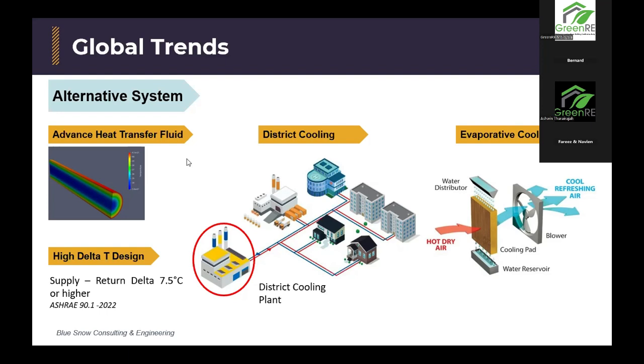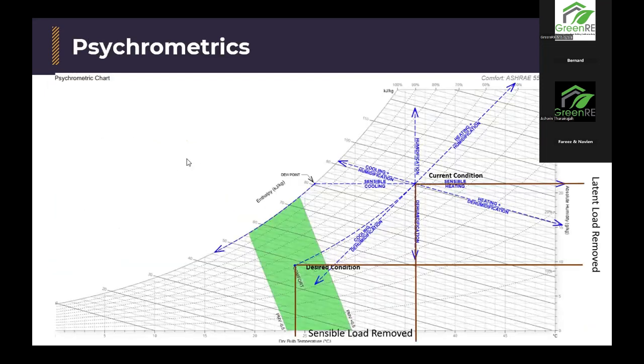Evaporative cooling is using water and having air run through it, evaporating the water droplets into cooler air. But the caveat is evaporative cooling will increase humidity. That's a given. If you go later, I'll share the slides. You can actually go back to some of the psychrometrics. You'll see that arrow that I showed here. Yeah, evaporative cooling does this.